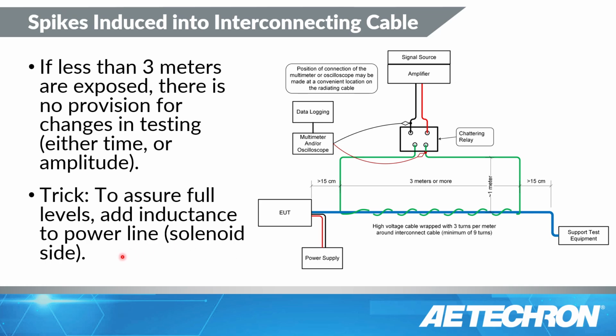Now, we've had people talk about the fact they cannot obtain 600 volt spikes off of this relay. And there are two reasons why that may occur. One, you're not using very much cable here. Maybe you've minimized this cable length. And as a result, that shorter cable has less inductance. Now, that's fine, but it's a combination of the inductive kick from the solenoid and from the wire that wants to arc across the contacts of this relay. If you find that you're having trouble with obtaining the 600 volt spike, simply place an inductance in one of these wires, and adding that inductance to that wire will also add inductance to this relay coil, and that will increase that inductive kick through the contacts, and you will likely have a much higher voltage as a result.